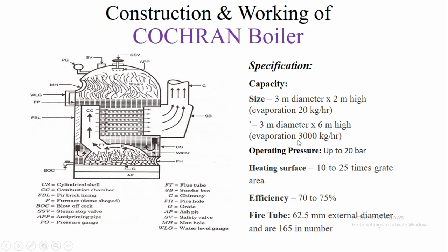The operating pressure is up to 20 bar. The heating surface is 10 to 25 times the grate area, and efficiency is around 70 to 75 percent. This is a fire tube boiler — specifically a vertical, multi-tubular fire tube boiler.